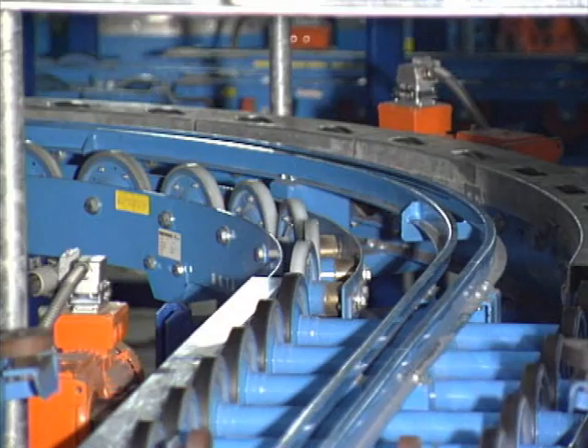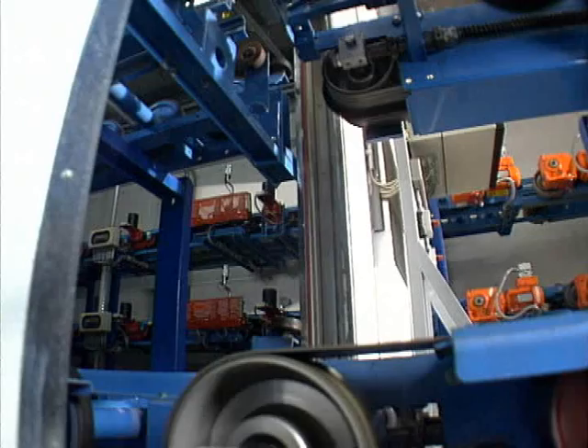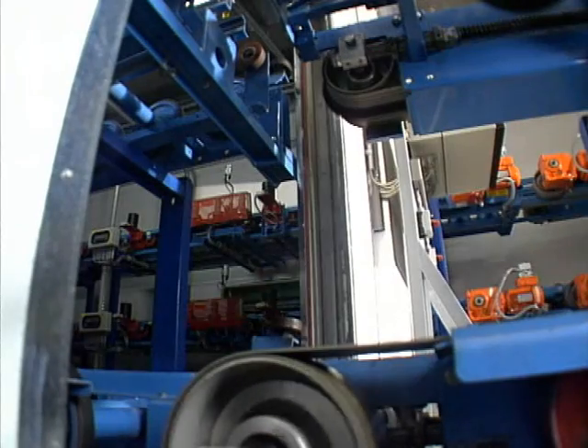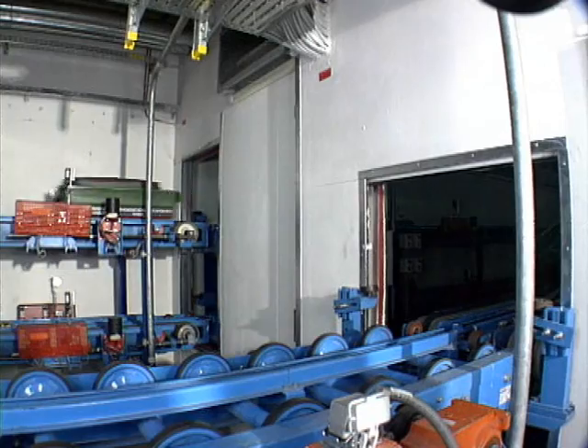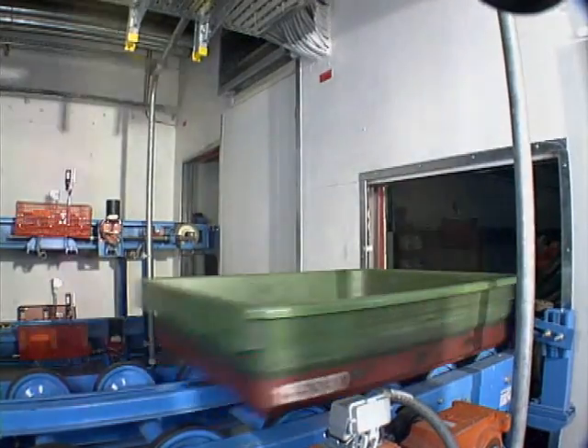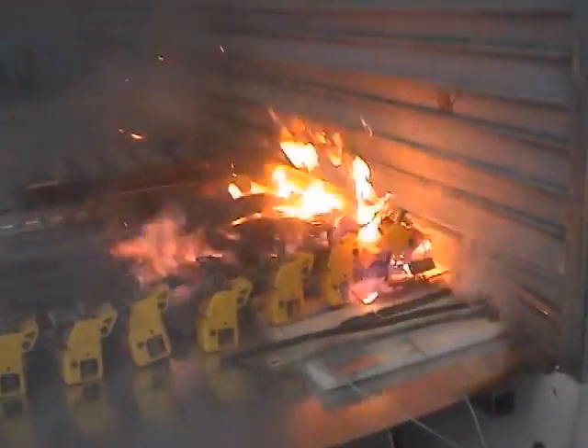A combination of special materials enables to shut off the continuing metal parts in such a way that the temperature of the side, which is not exposed to the fire, does not exceed 180 degrees Celsius. This know-how guarantees that parts on that side, which is not exposed to the fire, do not catch fire. The danger becomes evident during a fire test.